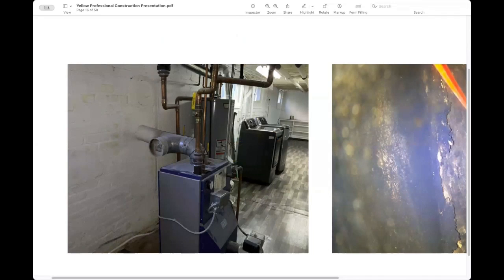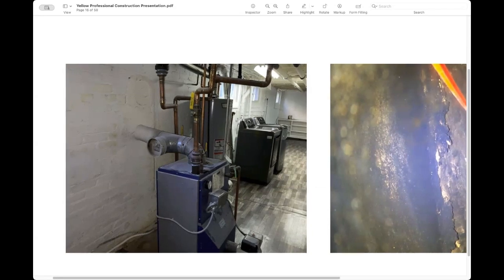And these pictures are actually paired because this oil burner, this oil boiler, looks pretty darn good. It's clean, it's tidy, the wall is nicely sealed. When I tap on the barometric damper, it was working great. But and this is the barometric damper right here, right? Yes, and that is necessary for 98+% of oil burning equipment. So if you see this and your client says, what is this?